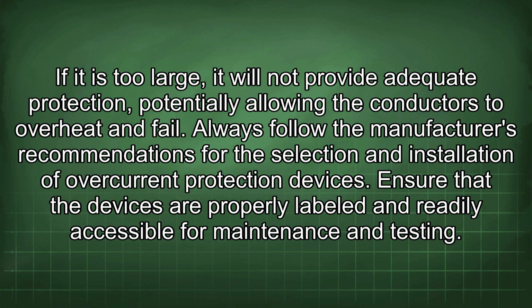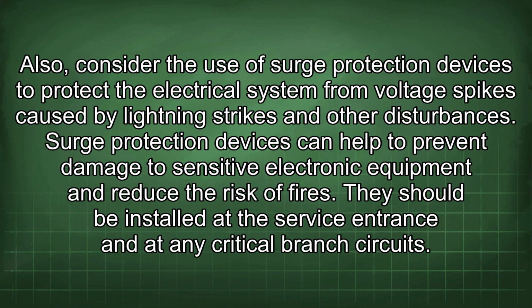Always follow the manufacturer's recommendations for the selection and installation of overcurrent protection devices. Ensure that the devices are properly labeled and readily accessible for maintenance and testing. Also, consider the use of surge protection devices to protect the electrical system from voltage spikes caused by lightning strikes and other disturbances. Surge protection devices can help to prevent damage to sensitive electronic equipment and reduce the risk of fires. They should be installed at the service entrance and at any critical branch circuit.